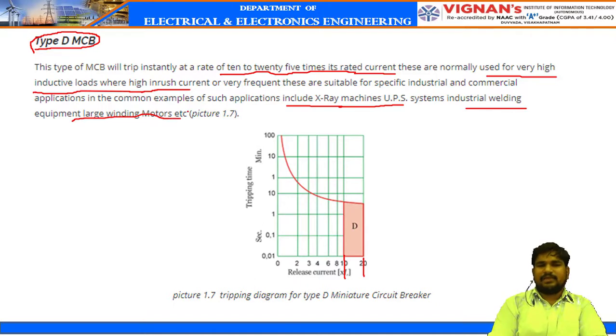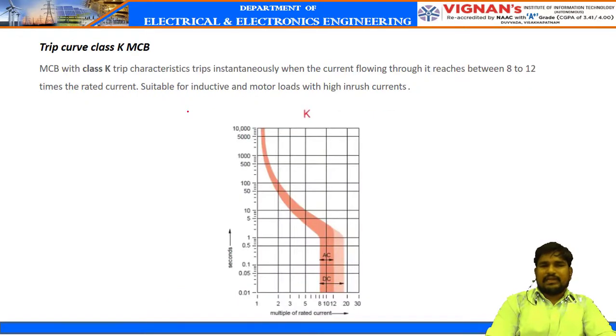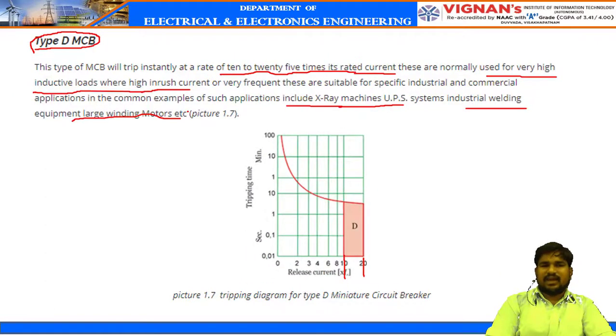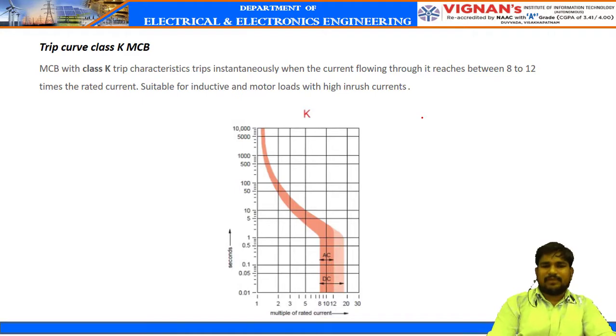Now, these type B, type C and type D are only used for AC systems. If you observe type K MCB, it will be useful for both AC and DC as well. In case of AC, it can withstand 8 to 12 times of rated current, but in case of DC, it is far more. It operates up to 18 times in case of DC.